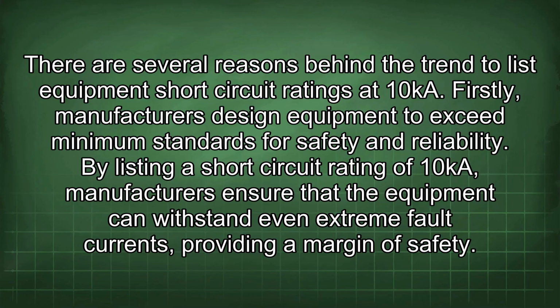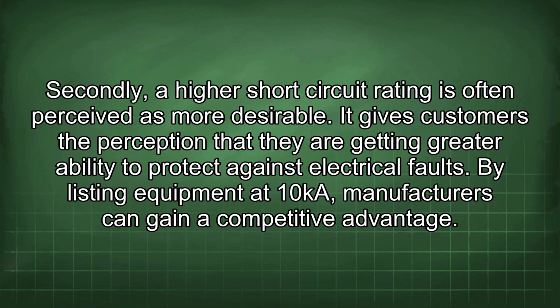There are several reasons behind the trend to list equipment short-circuit ratings at 10kA. Firstly, manufacturers design equipment to exceed minimum standards for safety and reliability. By listing a short-circuit rating of 10kA, manufacturers ensure that the equipment can withstand even extreme fault currents, providing a margin of safety.